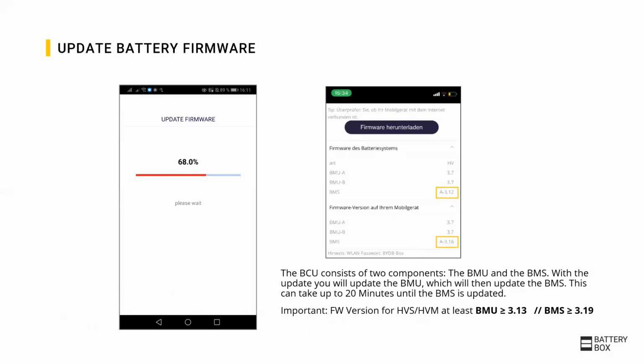When you are connected, update the firmware to the battery. You will see the versions in the app and on the battery. For the update, it is important to know that the BCU consists of two components, the BMU and the BMS. With the update, you will update immediately the BMU, which will then update the BMS. This can take up to 20 minutes until the BMS is updated, but you can already continue with the configuration. The firmware versions for the battery box HVS or HVM need to be at least BMU version 3.13 and BMS version 3.19.